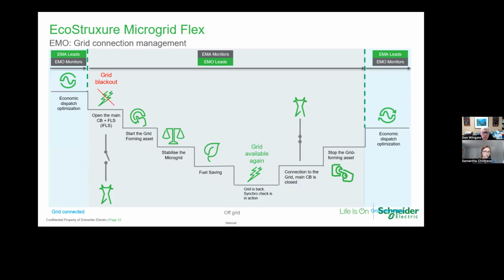During grid connected mode, we have our economic optimization. When the utility outage occurs, our microgrid controller opens the main breaker and starts our grid forming assets. Often a diesel generator comes on first. We bring on other resources too, such as the battery and solar PV, using all of those energy resources to stabilize the microgrid.